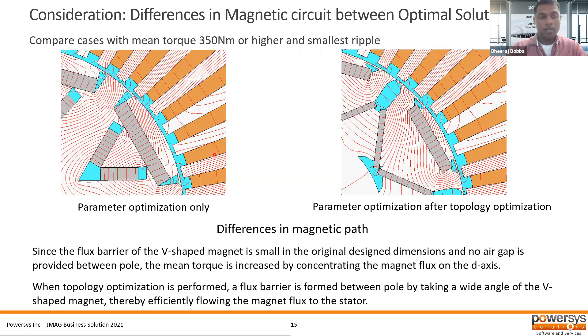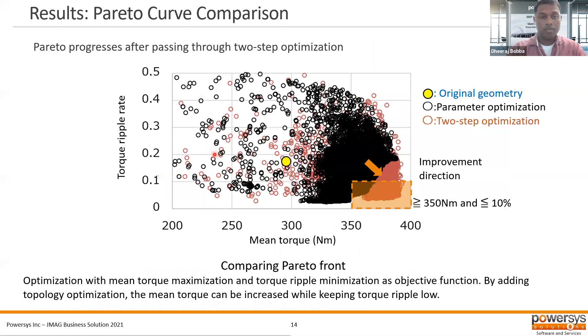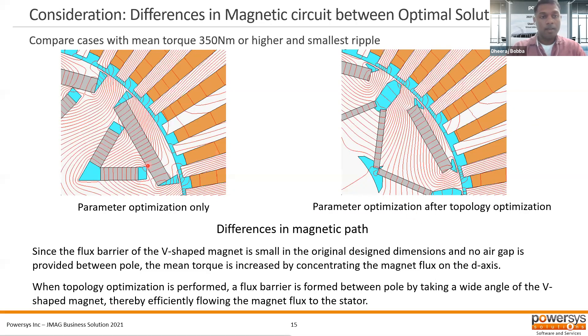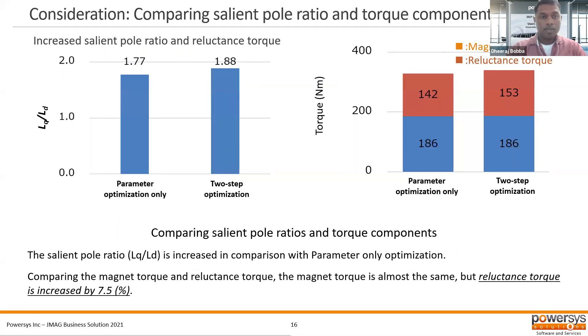Here we're looking at two examples on the Pareto front for both optimization steps — one from the black and one from the orange Pareto curve. We can see that the geometry is quite different, specifically the distribution of this V-shaped magnet. It's much wider here, and the flux barriers for the Q-axis is not well-defined. Here we have a really good bridge shape that focuses the flux all the way in the D-axis to the stator. The saliency of the machine is increased by the two-step optimization from 1.77 to 1.88, and the two-step optimization produced 7.5% more reluctance torque.